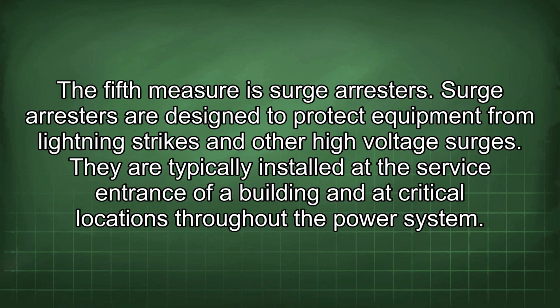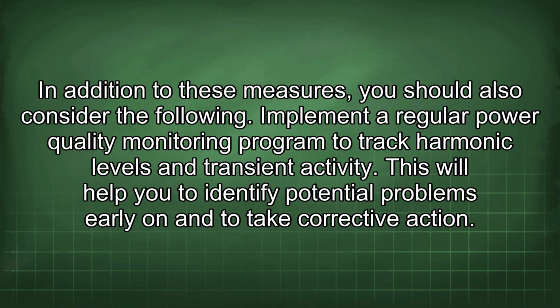The fifth measure is surge arresters. Surge arresters are designed to protect equipment from lightning strikes and other high-voltage surges. They are typically installed at the service entrance of a building and at critical locations throughout the power system. In addition to these measures, you should also consider the following. Implement a regular power quality monitoring program to track harmonic levels and transient activity. This will help you to identify potential problems early on and to take corrective action.